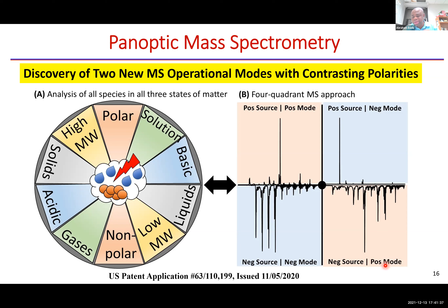And what I mean is that traditionally, we know that if your source is in a positive mode, we ask you to scan your mass spec in the positive mode. If your source is in a negative mode, we say scan your mass spec in the negative mode. So all we have is just 2 modes. It turns out that in the presence of the plasma, although your source might be in a positive mode, you are actually generating negative ions. So you can scan your mass spec in the mismatch polarity, positive and negative. You can also, whilst the source is in the negative, still scan your mass spec in the positive mode and get data.